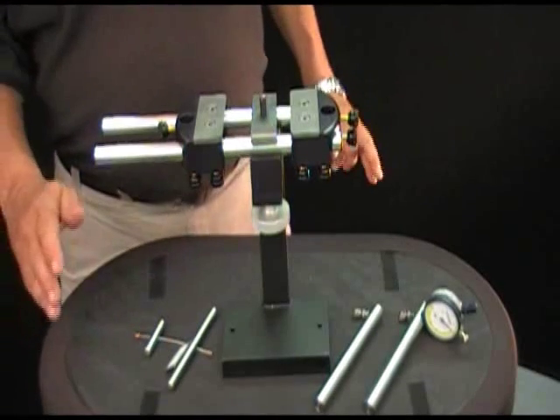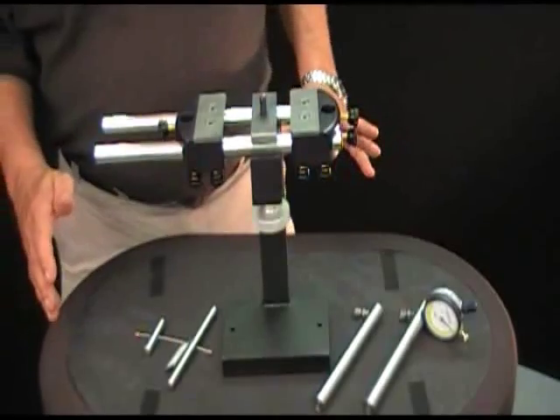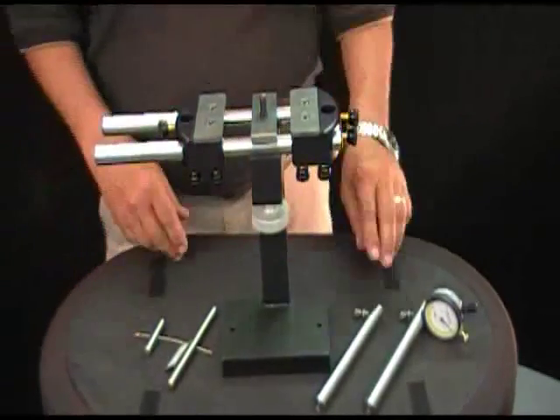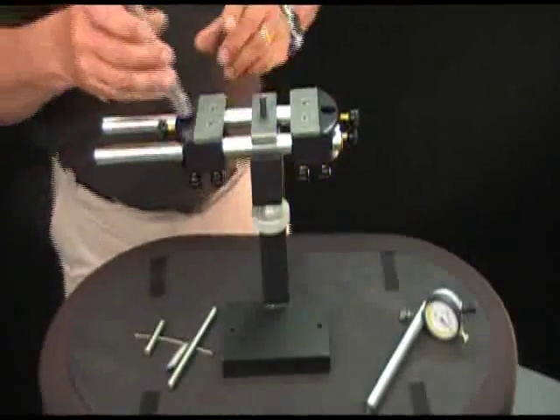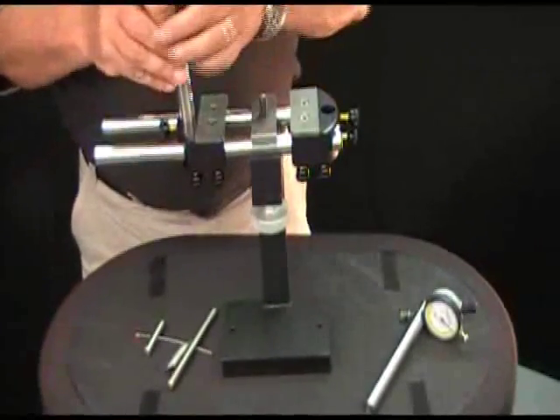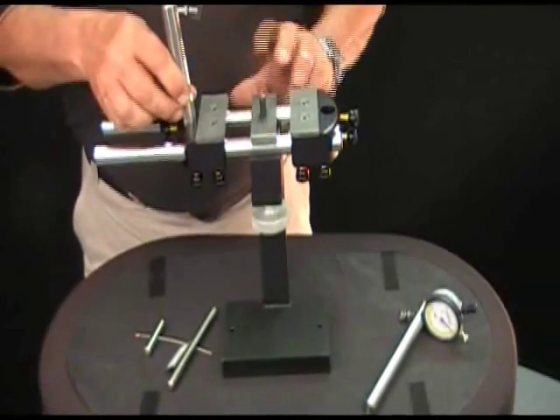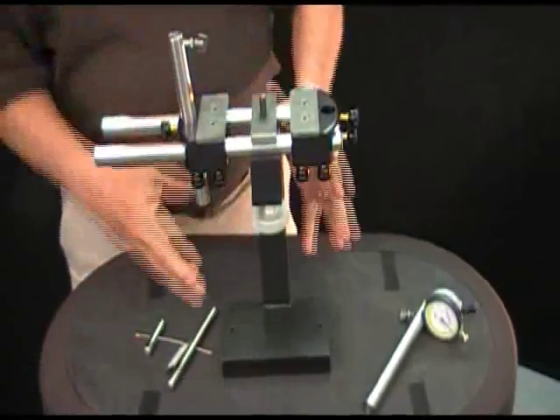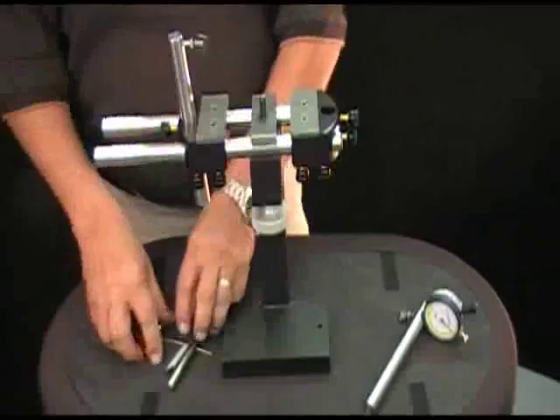Now that we've reviewed our setup sheet, we're going to set up the gauge to measure a 5 1/2 inch LTC pin. First, I'm going to take the lower arm. This is being held by the MRP gauge setting stand that lets both of your hands be free while you're doing the adjustment.